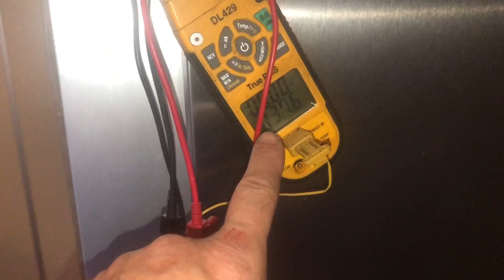All right, so it definitely had an iced up coil - that was the problem. Cabinet sensor is bad, reading way high. This one's going to get by, it's not perfect - the supply's getting a lot colder than the return coming out. That's a good TD though, and it'll keep it working so they can use this till I can get them the cabinet sensor. Today's Saturday, I can't even order the part till Monday, which means I won't get it till Wednesday.